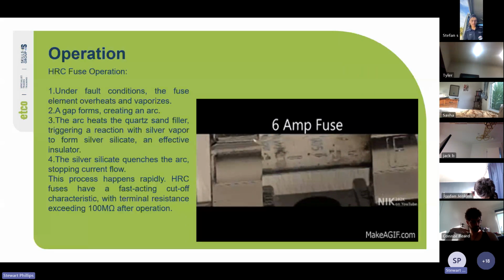Under fault conditions, the fuse element overheats and vaporizes. A gap forms, creating an arc. The arc heats the quartz sand filler, triggering a reaction with silver vapor to form silver silicate, which is a very effective insulator. The silver silicate quenches the arc, stopping current flow. This process happens rapidly. HRC fuses have a fast-acting cutoff characteristic with terminal resistance exceeding 100 megaohms after operation.